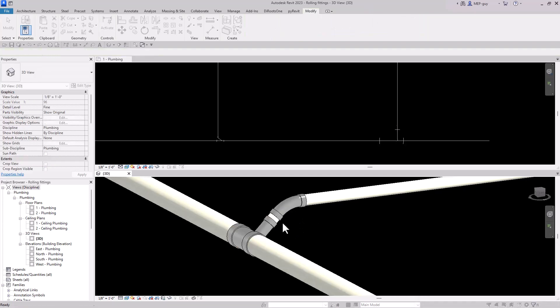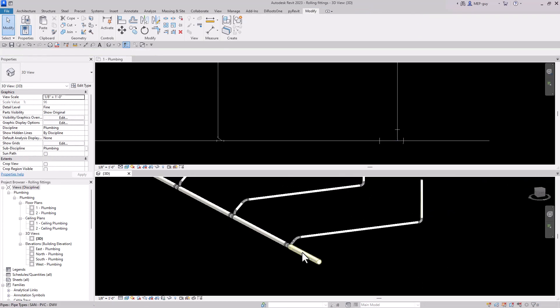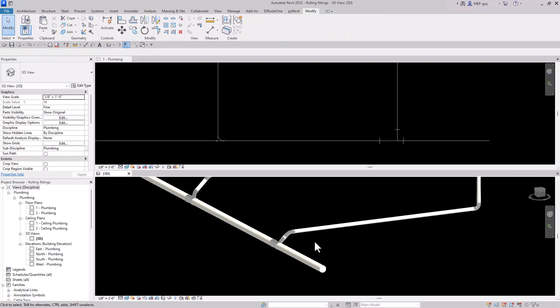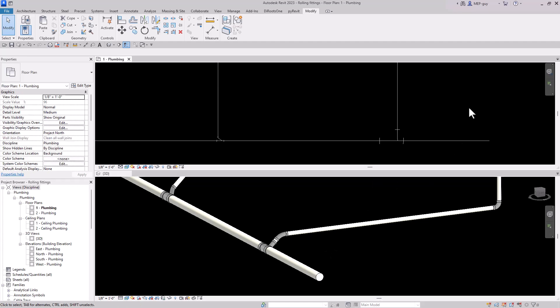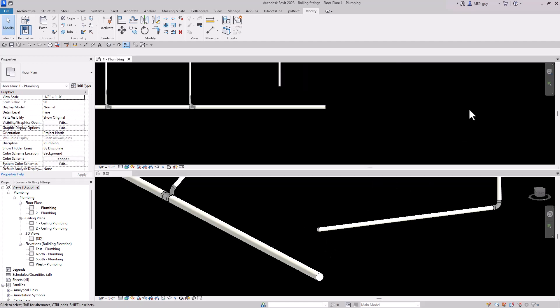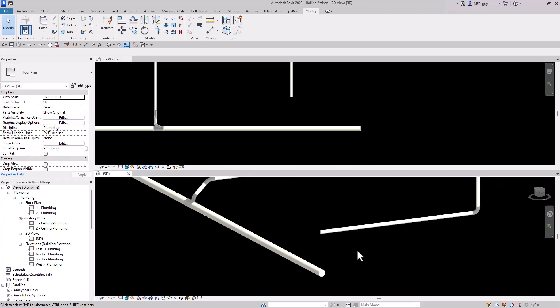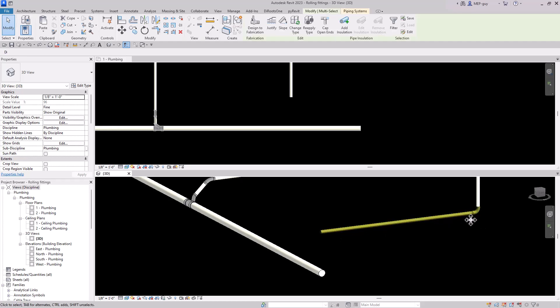I'll hit Cancel and undo everything with Control Z back to the start. We could change it to a sanitary tee, but that's not actually a legal fitting per the International Plumbing Code. So instead, I'm just going to redraw this piping. Sometimes — actually a lot of times in Revit — it is just easier to redraw piping. I'm going to delete these pieces.